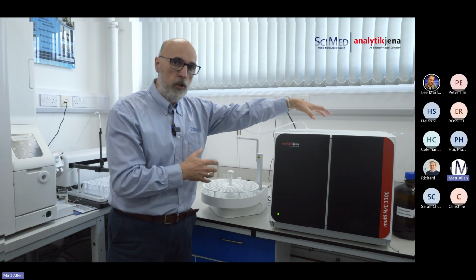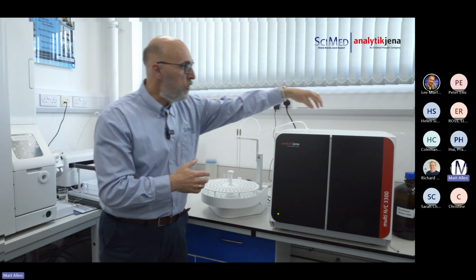The 2300 has a different injection mechanism, which I'll explain in a bit more detail in a moment. But the auto sampler sits on the top of the instrument because it only has to travel a very short distance to the injection chamber. That has 2 rack options. There's a 60 position, which uses 8 ml vials, and there's a 112 position, which uses standard 2 ml HPLC vials. So those are the options regarding the auto sampler. So now Rich is going to show you how to set up the method within the software.